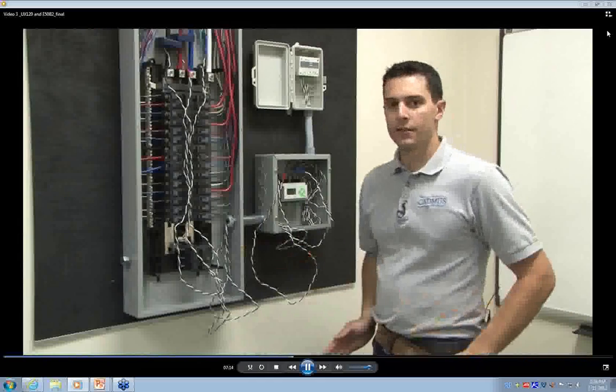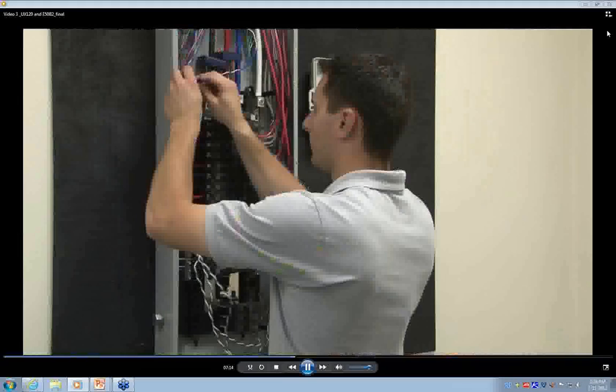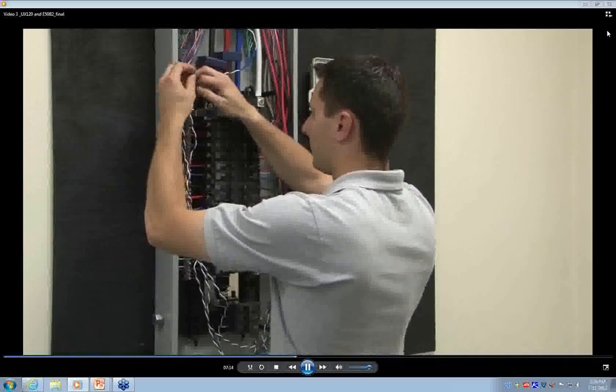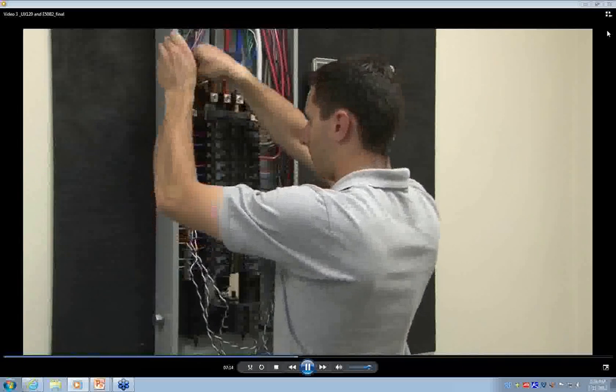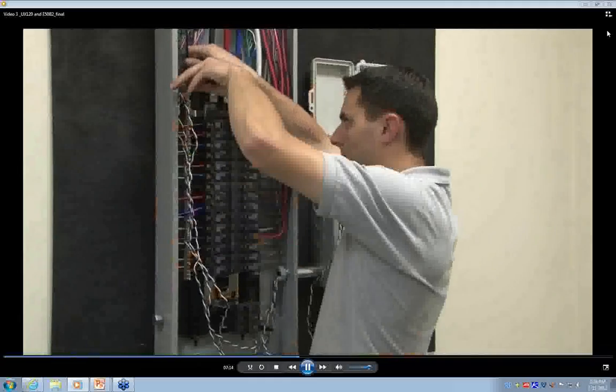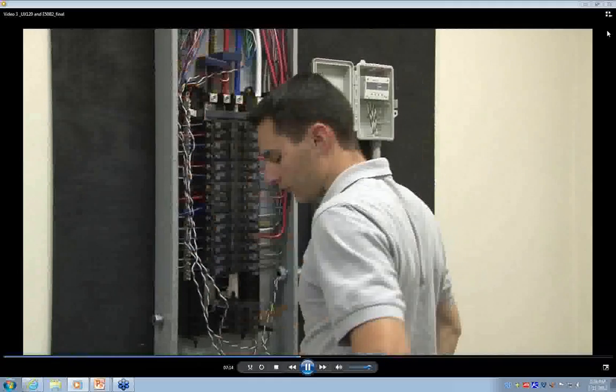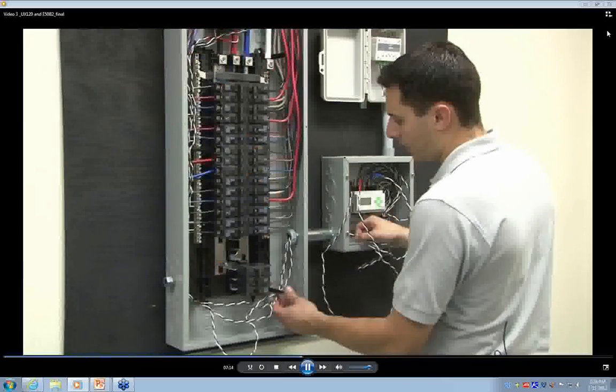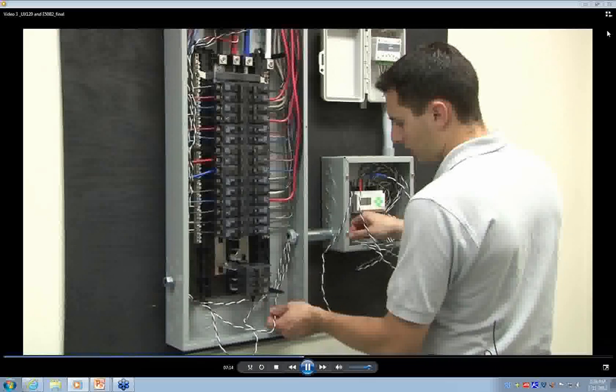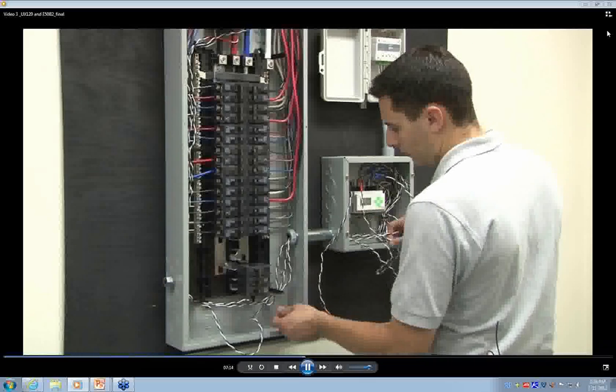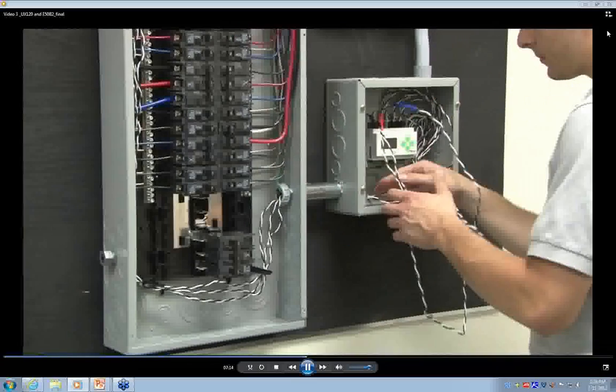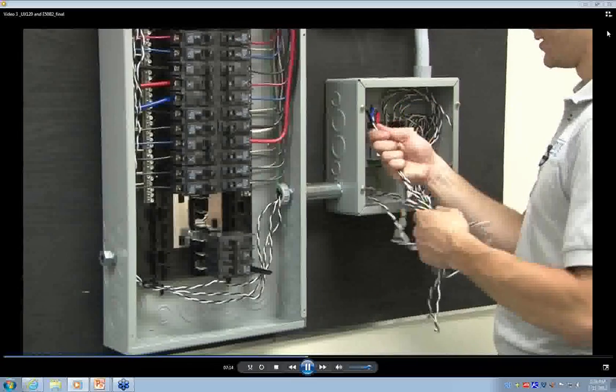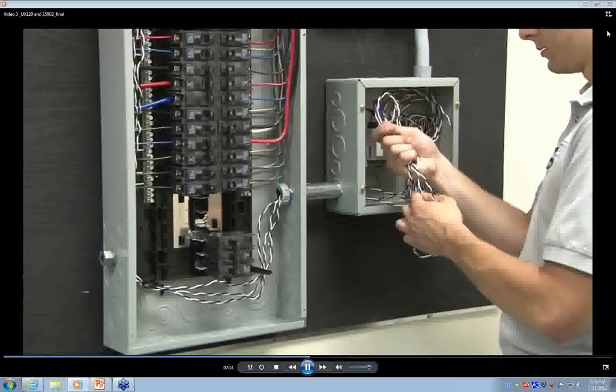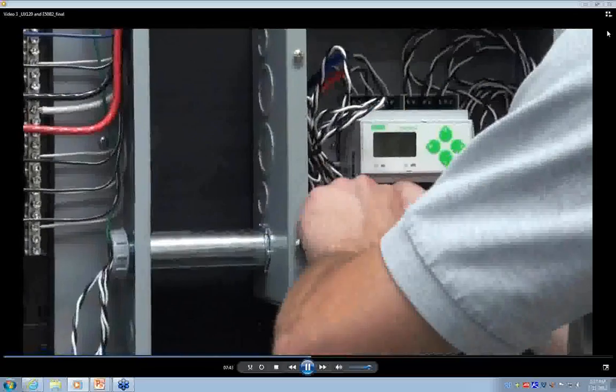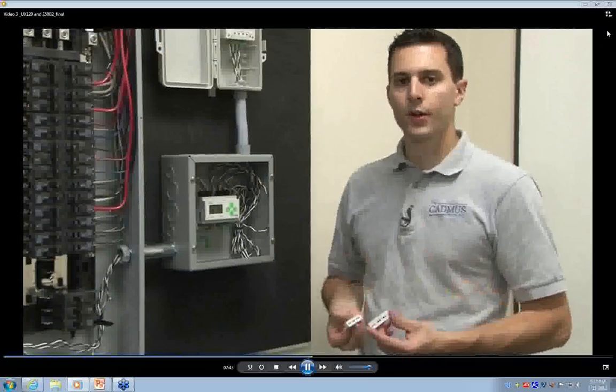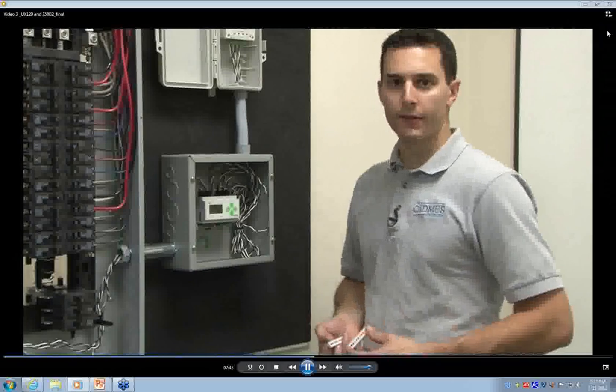Now that all of our CTs are installed, we can organize them with zip ties. And we'll pull the excess wiring into the enclosure. And once again, we'll organize these conductors with a zip tie as well. We can now put our terminal covers back on the top terminals of our E50B2.